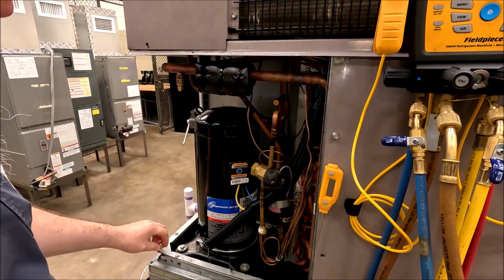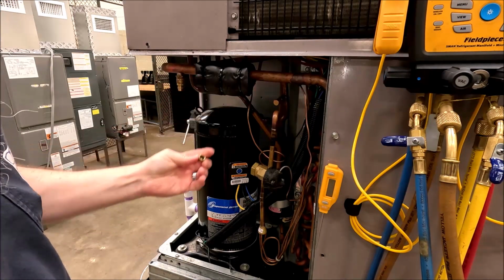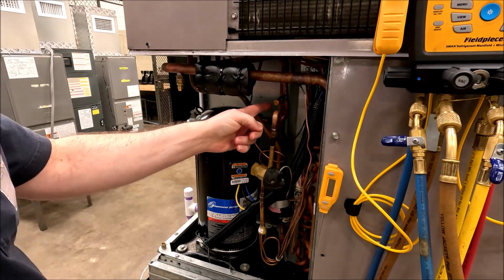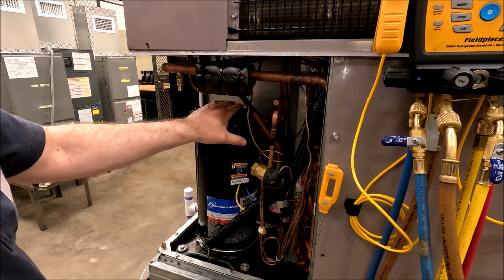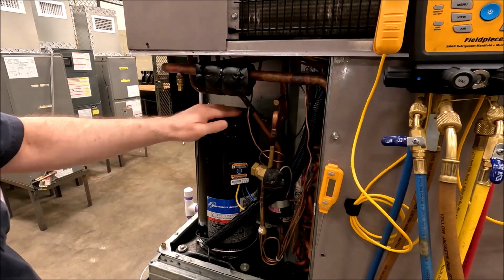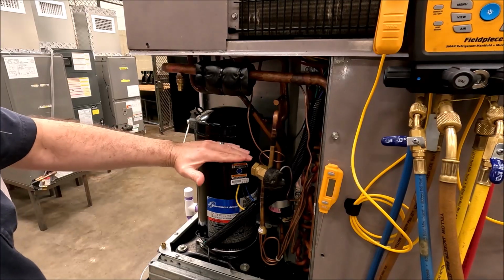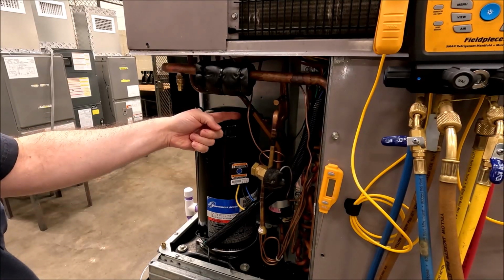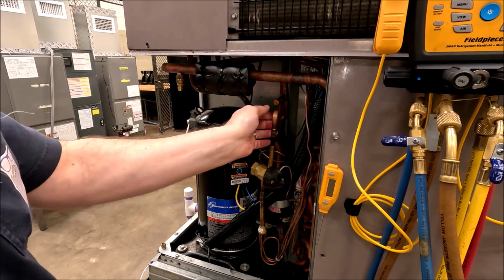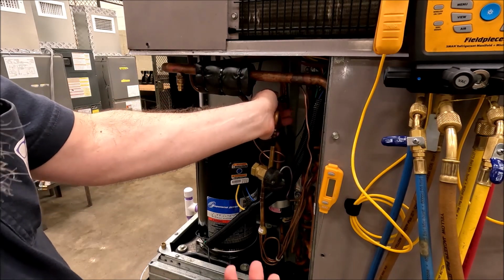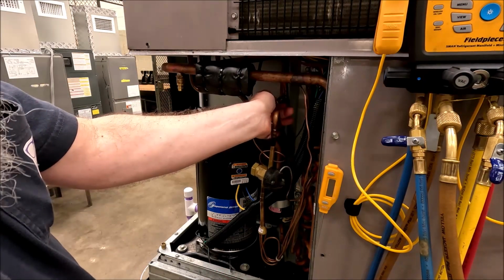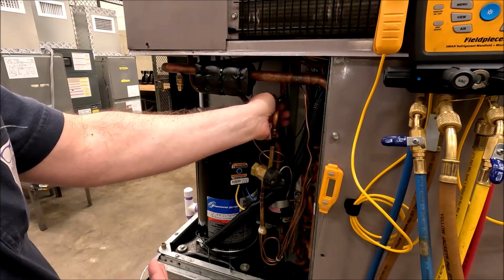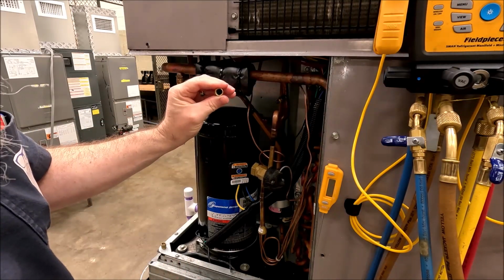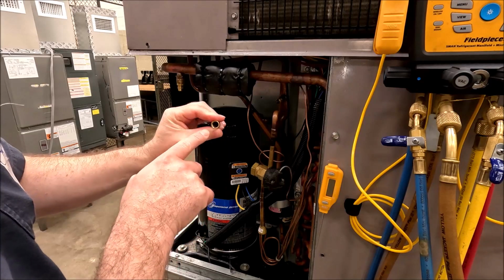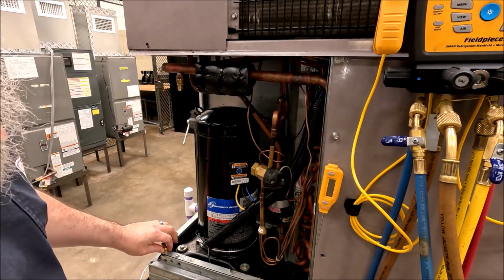And once again, I got my O-rings in my brass caps. They give us a high port, warm on top of the scroll. My scrolls are compressing like right here. So the discharge gas is coming out, discharge vapor. Compressor's a vapor pump, you gotta remember that. We don't like liquid in it. Scrolls might can handle a little bit, but they're definitely better than the old stuff, right? So I've got another brass cap right there.